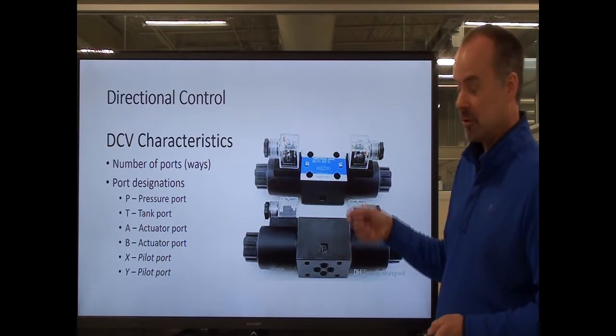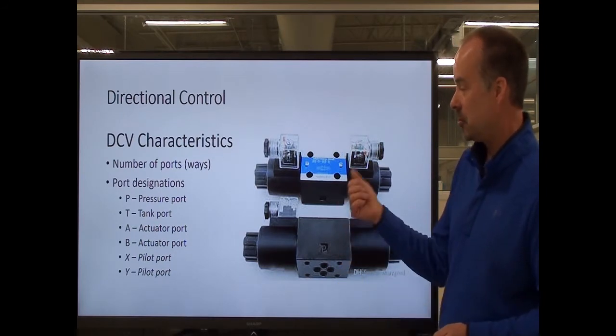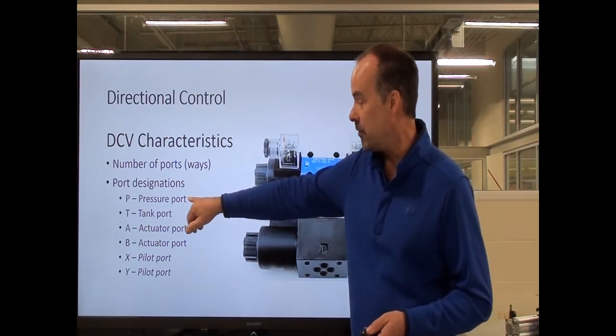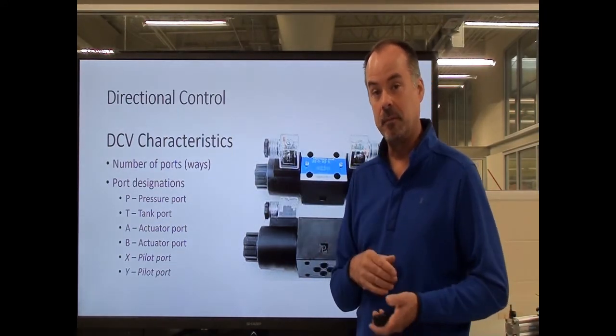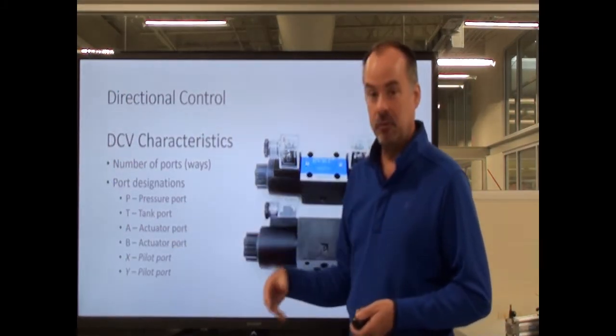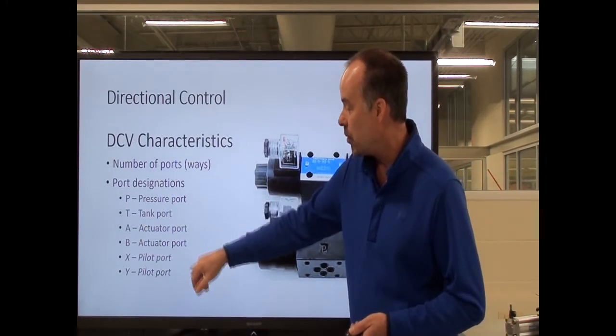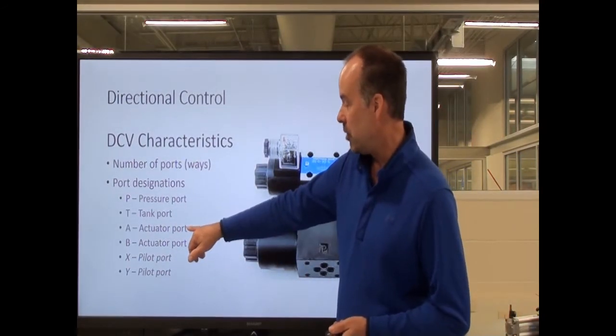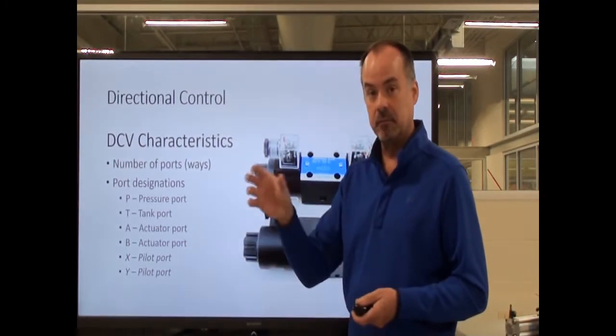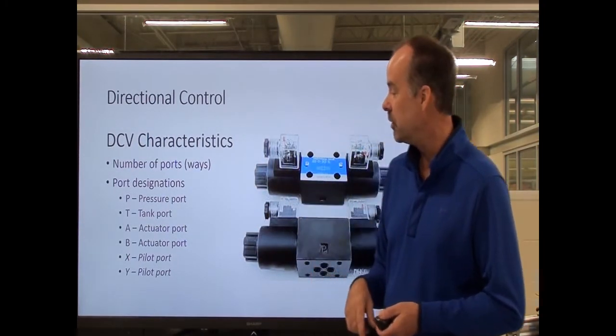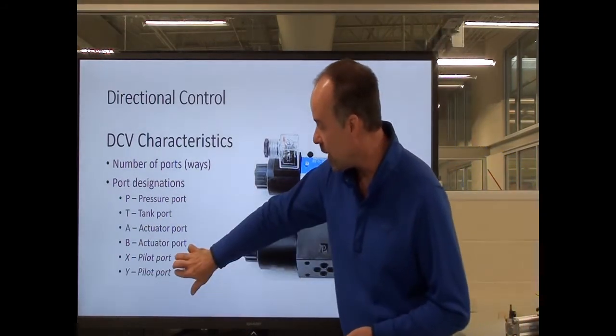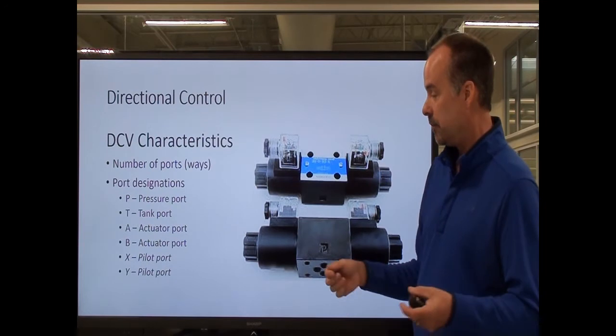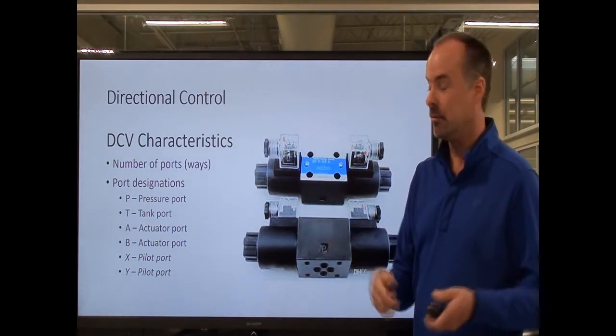The port designations: your valve will have a pressure port on the side connected to the pump of your hydraulic system. The tank port is plumbed back to your reservoir. The A and B ports are your actuator ports — if I'm moving a hydraulic cylinder, one side may be hooked to A and the other to B, to allow the fluid to pressurize each side of the cylinder based on the position of the spool. And on a pilot-operated valve, you'll find X and Y ports — the ports that actually move the spool are labeled X and Y.